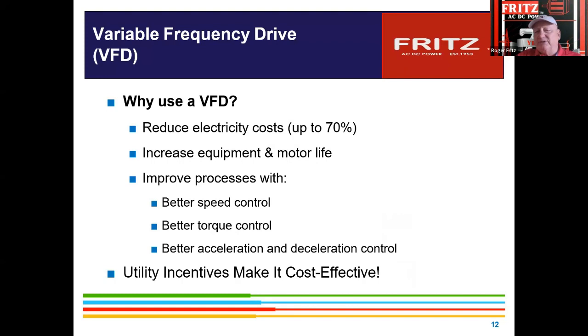Why use it? Reduce electricity costs by up to 70%, especially on very lightly loaded motors or fans and pumps, because of the cube law. It increases motor and equipment life, because you're unloading. At some of the facilities we've done in plastic processing, we've taken a 2,500 amp service, and after we put drive controls on a majority of the motors on that system, it ended up being around 1,000 amps of current draw at the end. So it does have some big impact. It improves the process, controlling torque and speed and pumps and flows. It also takes a lot of decibel noise out. We've seen a lot of facilities that don't require hearing protection gear anymore, because it's brought the decibel level of the whole factory down.